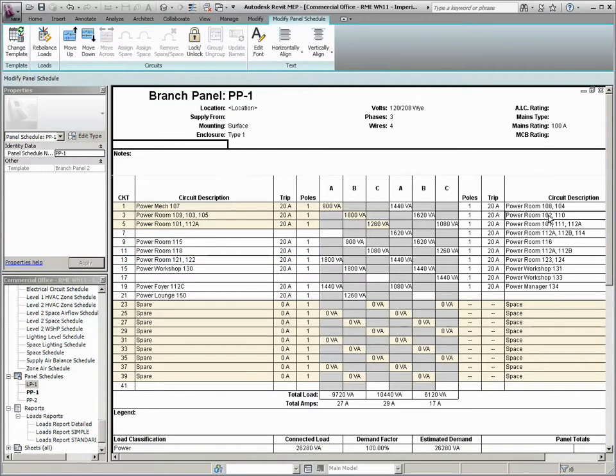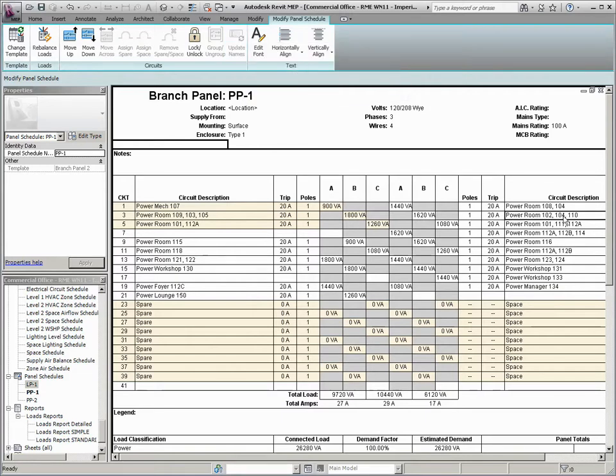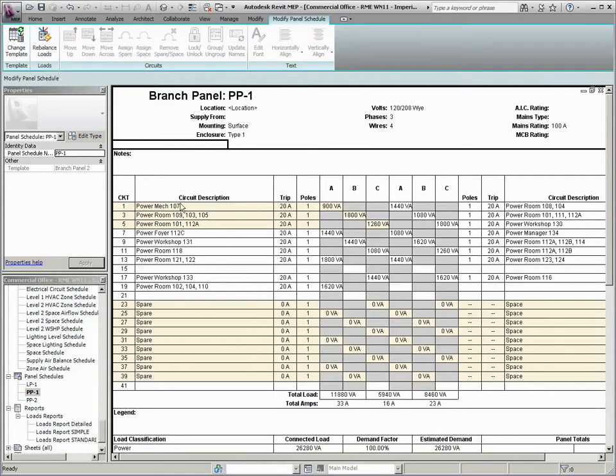Those other circuits can also be grouped or ungrouped, and in the circuit description, the name can be updated automatically by using a simple tool here. So when you balance the panel schedule, all the information and the circuits that you've locked remain where they are, and the updated name information for the circuit descriptions match the circuit that it's been reassigned to.